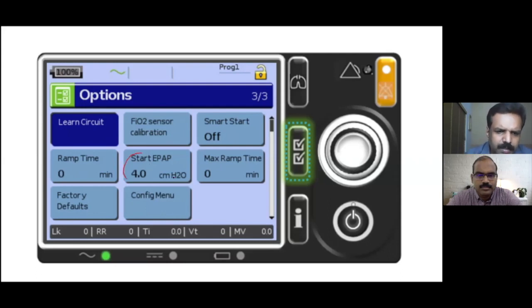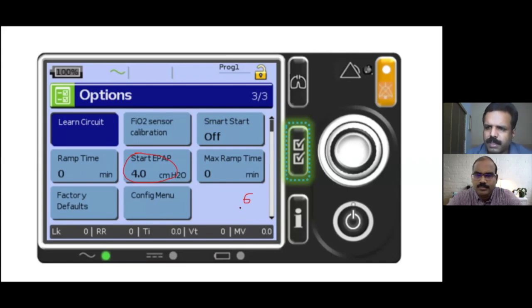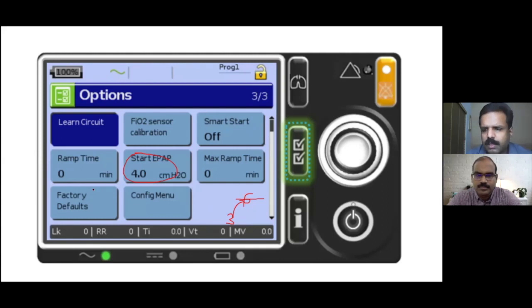Start EPAP refers to the initial pressure from which the machine begins. For example, if EPAP is set to 6, the machine can start at 3 and gradually ramp up to 6. The ramp time determines how long this gradual increase takes. This improves patient comfort — initially minimal pressure, then gradually building up. When setting the ventilator, always set a start EPAP, then the target EPAP, and configure the ramp time accordingly.